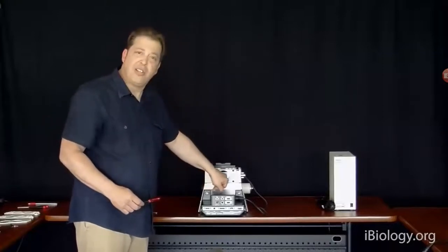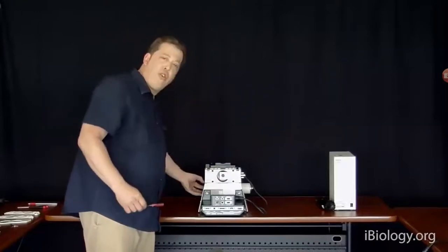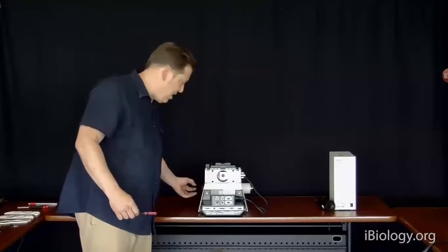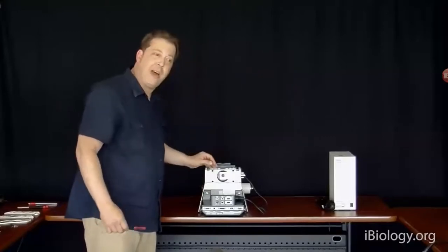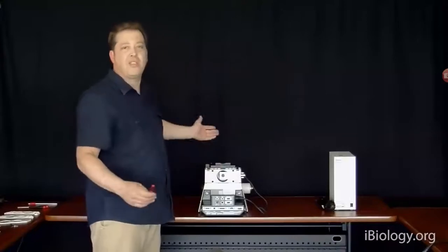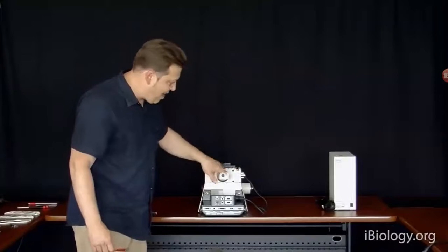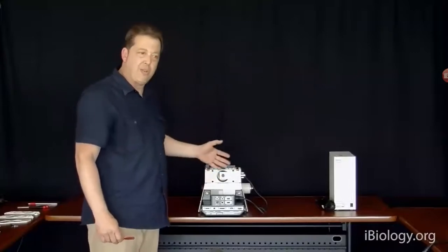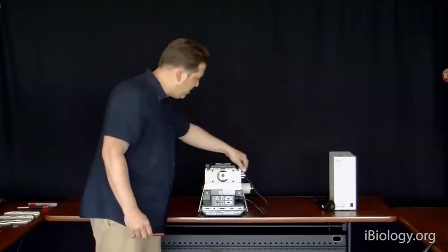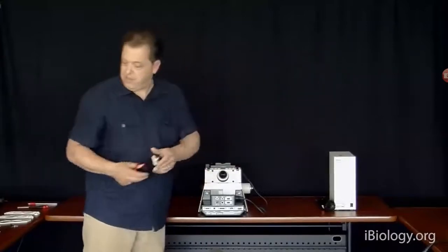and I focused at this, I'd have a spot of laser light, and then I could put a confocal or parfocal detector at the image plane on the side of the microscope, which we'll talk about in a little bit, and detect the photons point by point as I move the stage. So a simple stage scanning confocal microscope. Okay, so it's very useful to have these accessible planes in the microscope and know how to take advantage of them for these types of techniques. So that's our field iris.